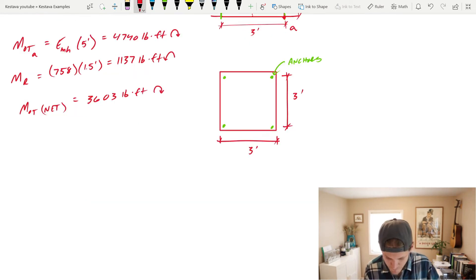Next, I've shown us a plan view and where anchors are located. So we have four total, one in each corner. And I know that I said that the actual in-plan dimensions of the unit is three by three. And that means the anchors are going to be spaced slightly less than that, you know, maybe two foot eight inches or something, which would change our calculations. But for simplicity sake, just assume that the anchors are also spaced three feet apart.